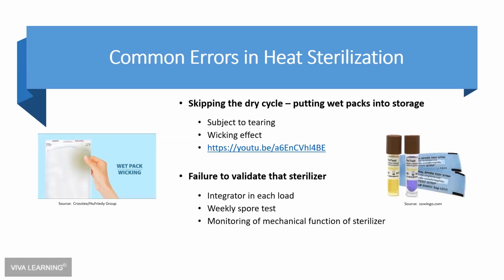Lots of practices still are not aware of changes that were made a very long time ago to monitoring or validating your sterilizer. First and foremost, the CDC guidelines say you need to put an indicating integrator, class 5, I'll talk about what that means, in each load. That validates that the load met the parameters for sterilization: time, pressure or steam penetration, and temperature. That's per load. Then you need to do a weekly spore test. When the 2003 CDC guidelines came out, the recommendation was monthly, but that's been changed for a very long time. So it's a weekly spore test, and you should also be monitoring the mechanical function of your sterilizer.